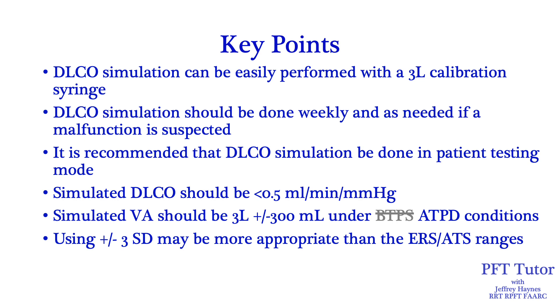Key points: DLCO simulation can be easily performed with a 3-liter calibration syringe. DLCO simulation should be done weekly and as needed if a malfunction is suspected. It is recommended that DLCO simulation testing be done in patient testing mode. Simulated DLCO should be less than 0.5 mL per minute per mmHg. The simulated VA should be 3 liters plus or minus 300 mL — remember, under ATPD conditions, not BTPS. And as shown, using a 3 standard deviation range may be more appropriate than the ERS ATS ranges.